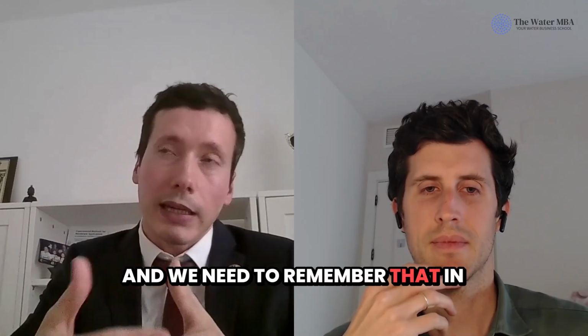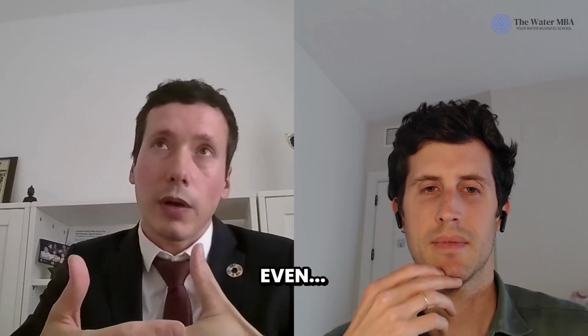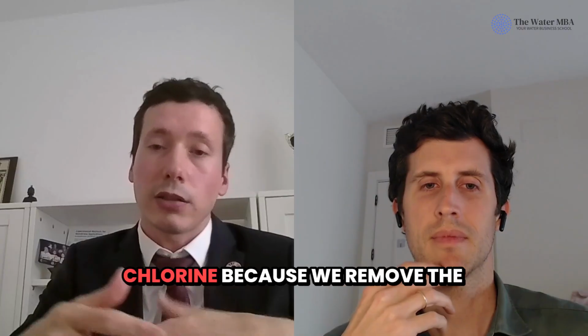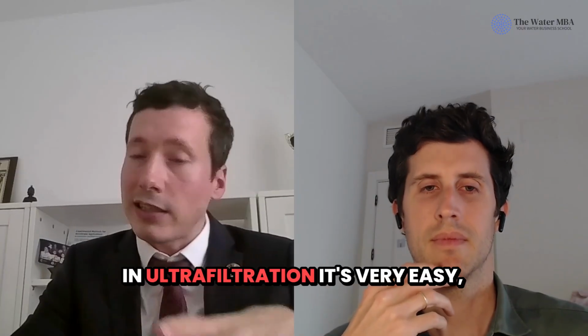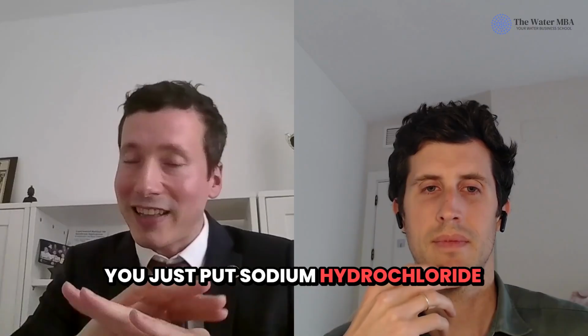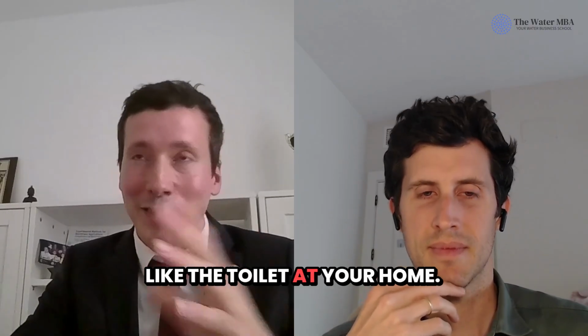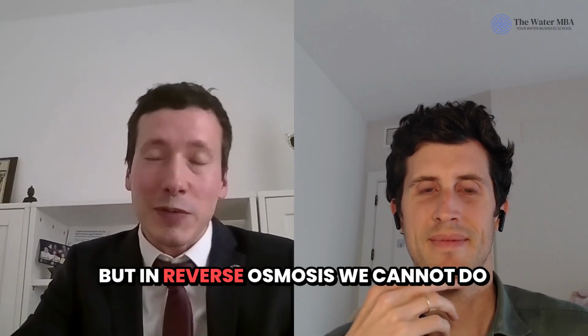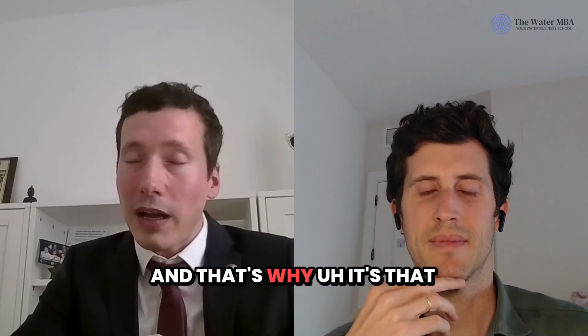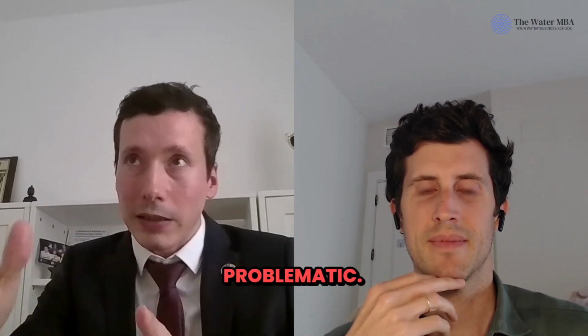And we need to remember that in reverse osmosis membranes, we cannot use bleach. We cannot use chlorine because we'll remove the polyamide. In ultrafiltration, it's very easy. You just put sodium hypochlorite and everything's clean, right? Like the toilet at your home. But in reverse osmosis, we cannot do that. And that's why it's that problematic.